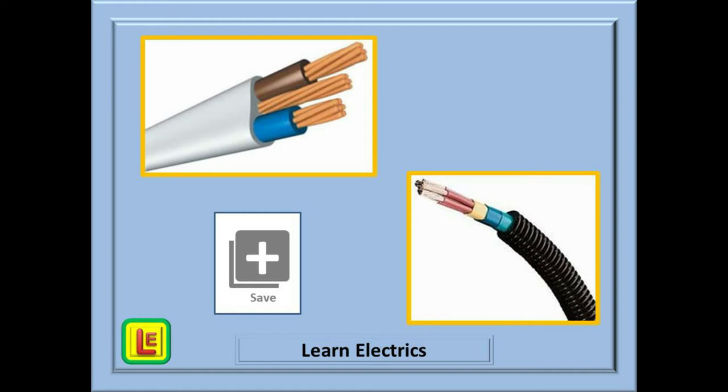The heat travels so slowly through the plastic that you do not burn your hands. The heat lost from the plastic conduit is reduced, and the heat is still there inside the conduit heating the cable up. The cables shown here in plastic conduit may very quickly exceed this 70 degree limit unless we take steps to limit the maximum current that flows through them.